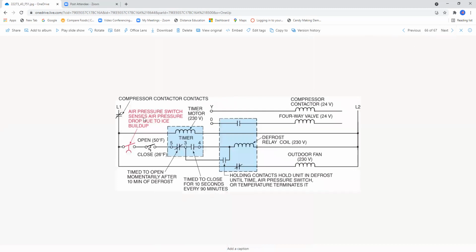Okay, the air pressure switch is going to detect blockage of airflow through the outdoor coil. And don't forget, the timer is designed to close for 10 seconds every 90 minutes of operation. And if this outdoor stat is not closed, basically we will not go into defrost. In this case here, we have an air pressure switch to sense ice buildup. So what happens is when this switch closes, because the outdoor coil is icing up, this will close. Obviously, the temperature will drop. And once it reaches the 90 minutes and the 10-second drops, if these two switches are closed, we go into defrost. It's as simple as that.